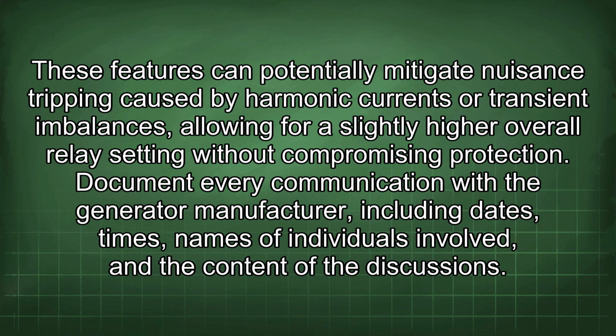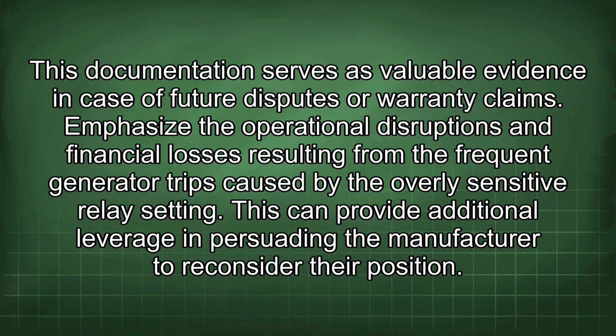Document every communication with the generator manufacturer, including dates, times, names of individuals involved, and the content of the discussions. This documentation serves as valuable evidence in case of future disputes or warranty claims. Emphasize the operational disruptions and financial losses resulting from the frequent generator trips caused by the overly sensitive relay setting. This can provide additional leverage in persuading the manufacturer to reconsider their position.